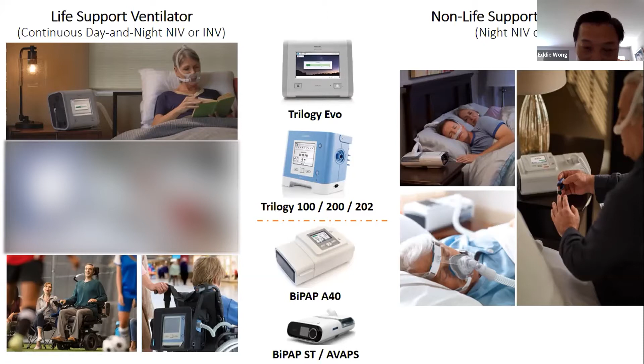So this is just to let you know, in brief, the specification difference between the life support ventilator and the non-life support ventilator. Like I mentioned earlier, a life support ventilator can perform invasive and non-invasive ventilation. A non-life support ventilator can only do non-invasive ventilation. And in terms of pressure, a life support ventilator can support up to 60 centimeters of water. Pressure means how much air can enter our lungs to promote oxygenation, depending on the pressure setting when the pressure mode is in use. So the higher the pressure that can go inside the lung, the more volume of air can enter the lungs.